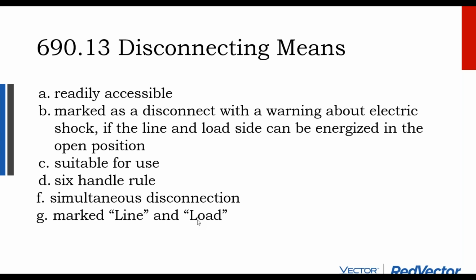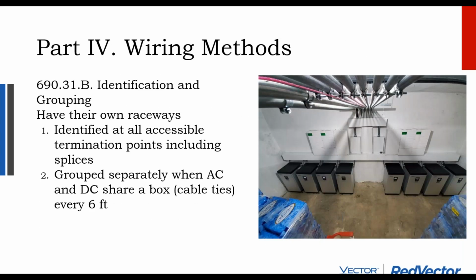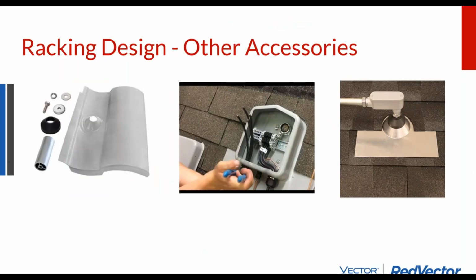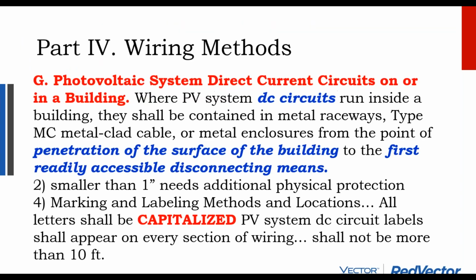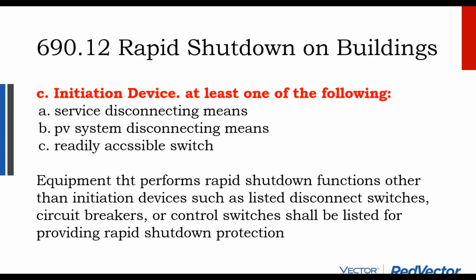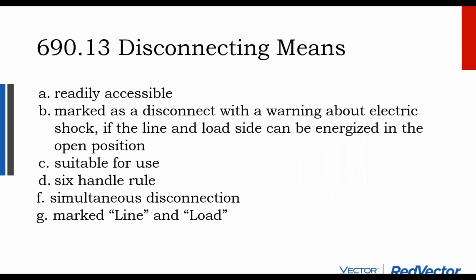And the reason is that the top of the switch is less accessible inside this knife switch disconnect. I think I have a picture. Well, I guess we'll talk about it later because I know there's a picture coming up, but it's all about that. If you're working inside the disconnect switch, the bottom side of the terminals are easier to contact than the top. So if that disconnect switch is thrown, one of those two sides is still going to be energized, and you want the energized side to be the least accessible side. And so the grid, the line, is always at the top of the switch, with the load, or in this case the solar array, being at the bottom of the switch.